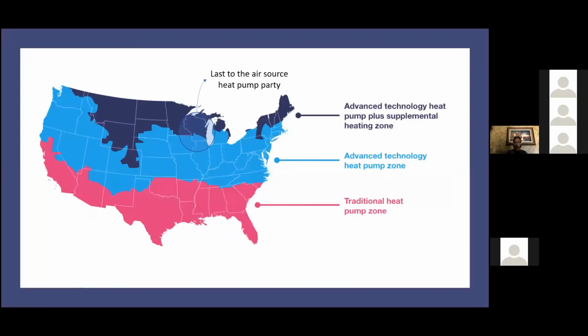so this is a great map I found. If you live in Mississippi or Louisiana or Texas, you're probably very familiar with heat pumps. Why? Well, for a new installation, you can do all your heating and all your cooling with the same unit. Because of your weather data, you're really not going to bump into a lot of times where the heat pump is going to struggle. So now this light blue part of the country has some heat pumps in it. For example, I have a friend in Kansas City, and he said about half the installations in Kansas City are heat pumps and the other half are furnaces.